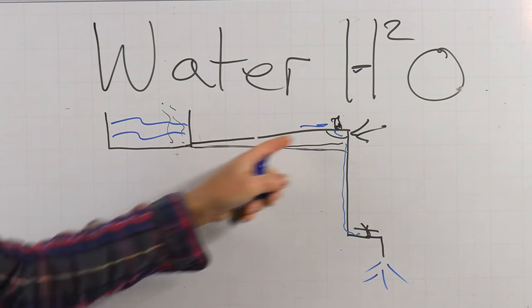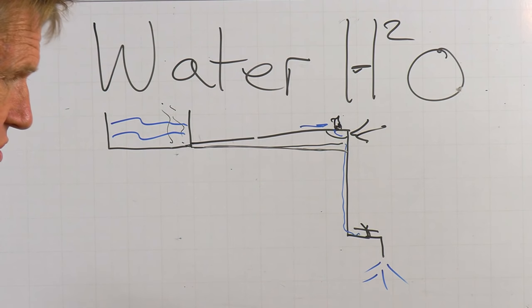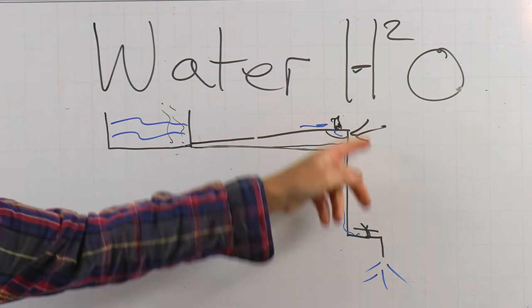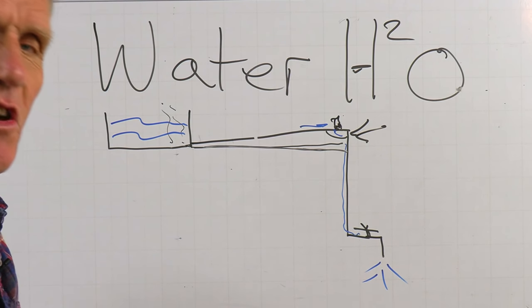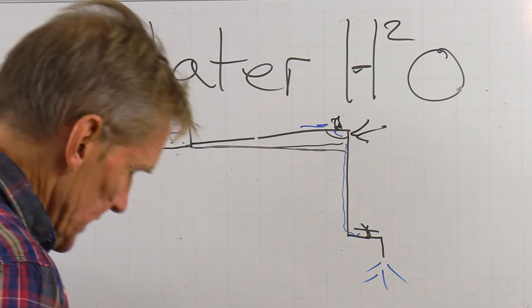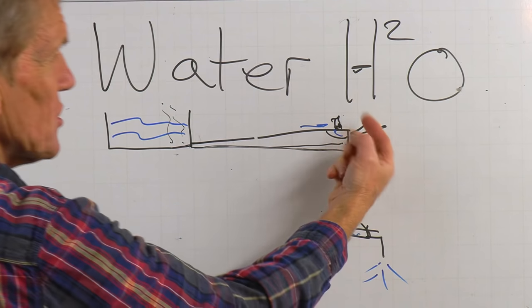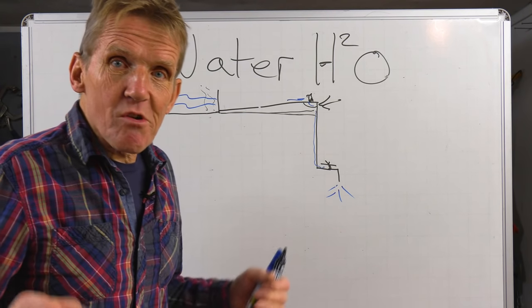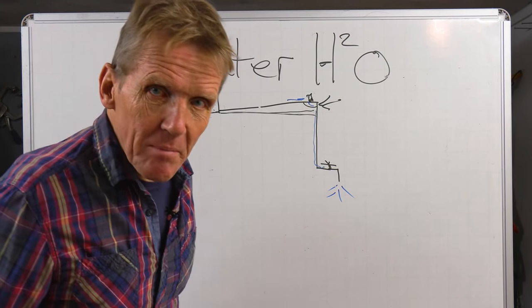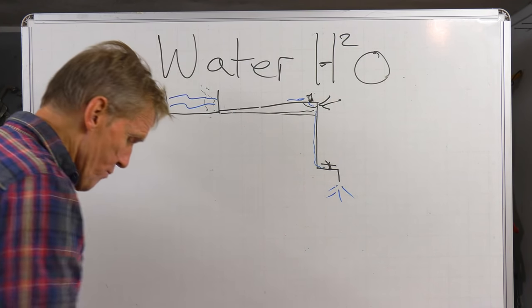Now, this can happen in a central heating system, it can happen in a hot water system, or a cold water system. The way I get rid of airlocks, if all we're trying to do is get the water running, and we're not worried about fixing the problem for good, if it's not a persistent airlock, then we don't worry. So what we then do is we just simply put some mains pressure on the end of a tap, blast it through there, and because mains pressure is more than that 9.8 meters that I spoke about, it will blast that airlock out, no problem at all.